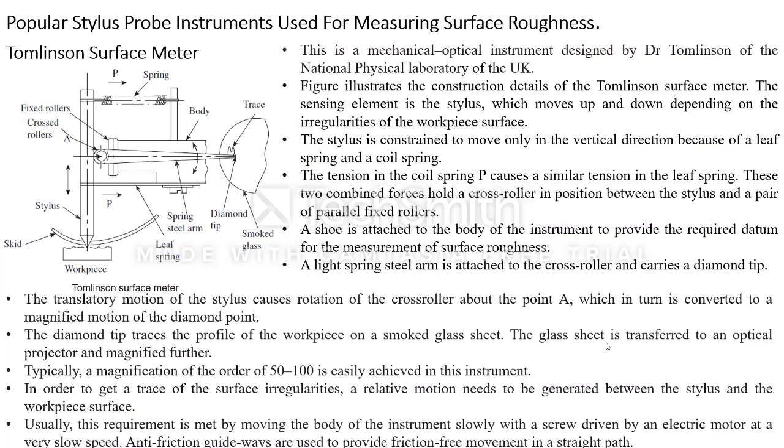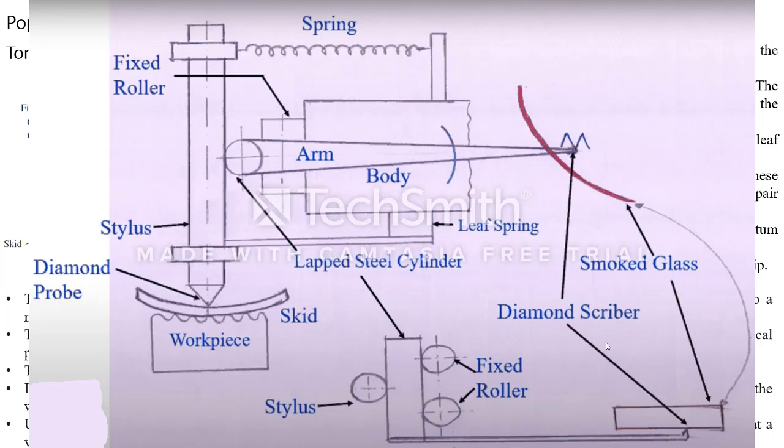In the previous lecture we have seen what is the Tomlinson surface meter, which is a popular stylus measurement instrument for the finish of a surface structure. This is a totally mechanical device working on mechanical principles — the workpiece is placed and connected to an electrical motor so the workpiece moves slowly, and this skid is used to support the stylus. The stylus has a diamond probe connected to the edge of the workpiece.